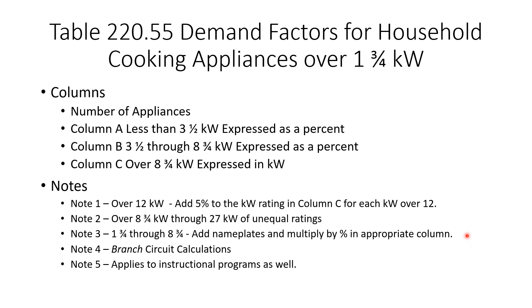Note 3 is important. For appliances between one and three-quarters and eight and three-quarters kilowatts, add the nameplates together and multiply by the percentage in the appropriate column. For example, three 3-kilowatt appliances: 3 × 3 = 9 kilowatts, then 70% of 9. If you have appliances in both Column A and Column B, do them separately and then add them together for the same feeder or service.